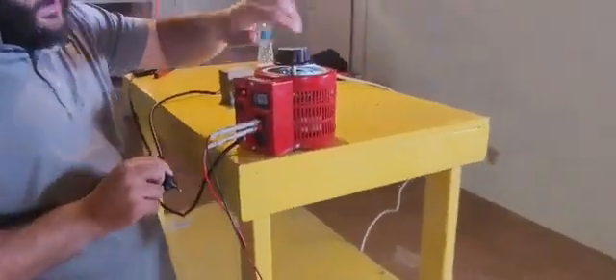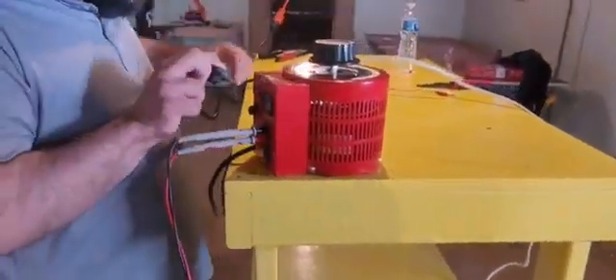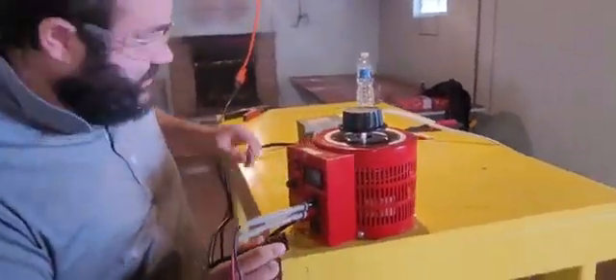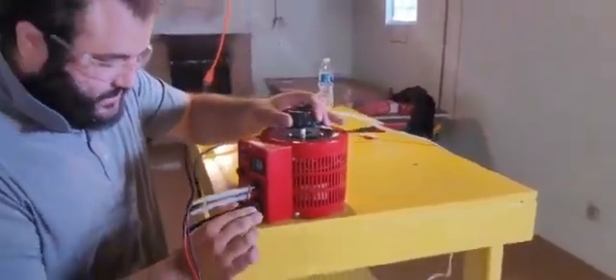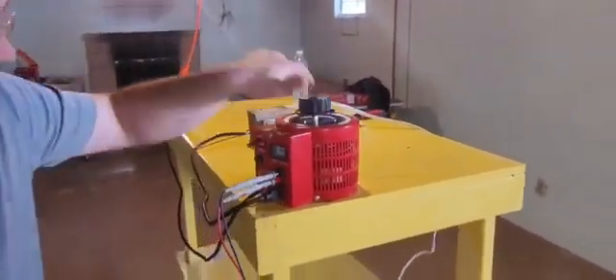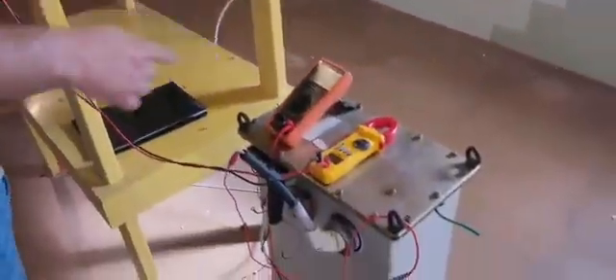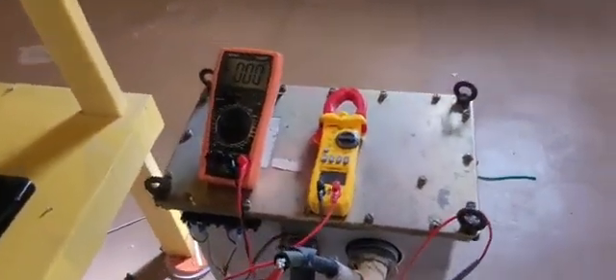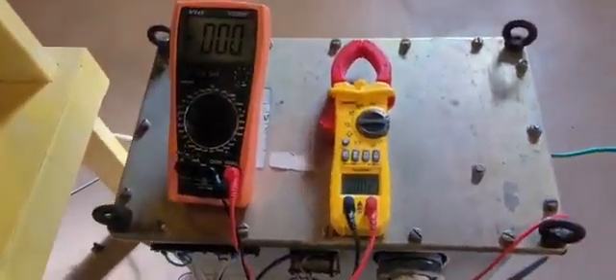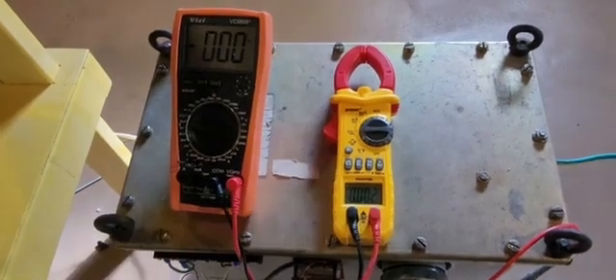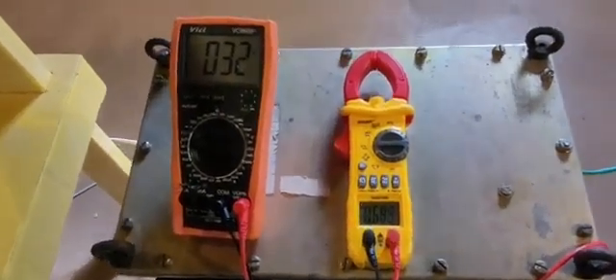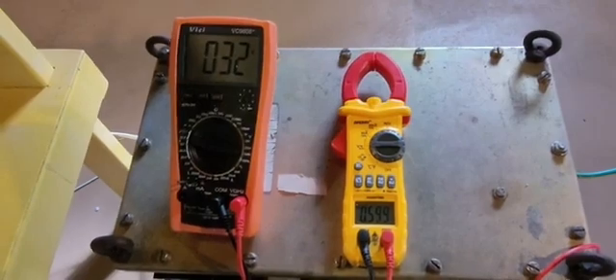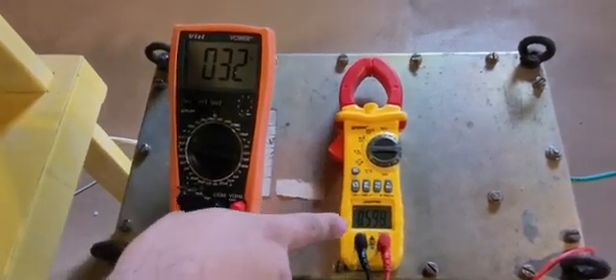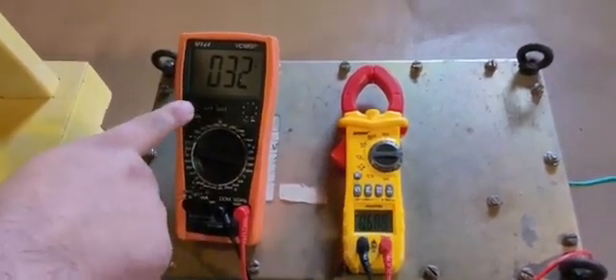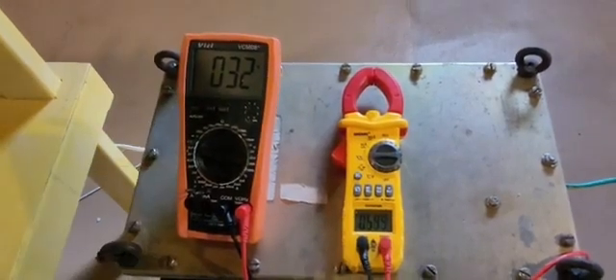And before I hook everything up, I make sure this is off. Make sure we're at 0. Take this, which is going to be feeding our X-ray generator, plug it in here, and we're going to turn it on. When we turn it on, you'll see our meters jump because of the residual voltage in the transformer, even though it is set to 0. Here we go. About exactly 0.6 volts AC is coming into the generator, as seen here, and we're getting 32 volts DC out of the X-ray generator, which is a pretty decent rise there.